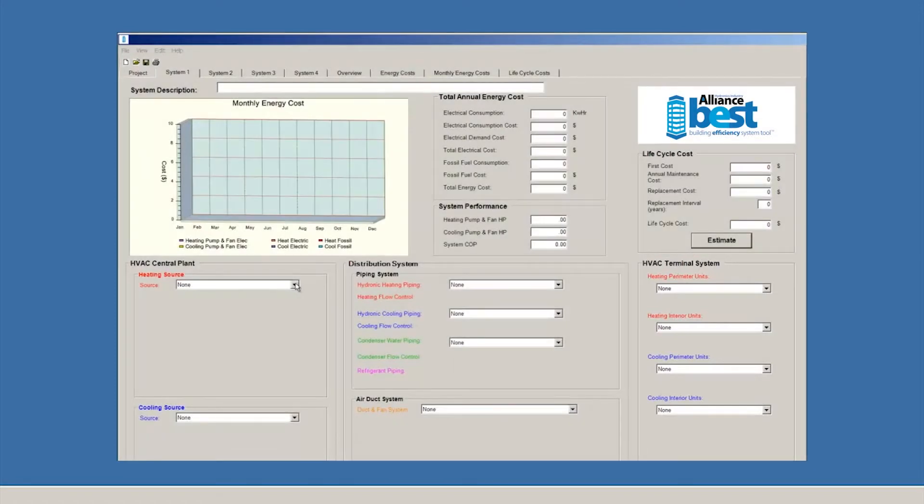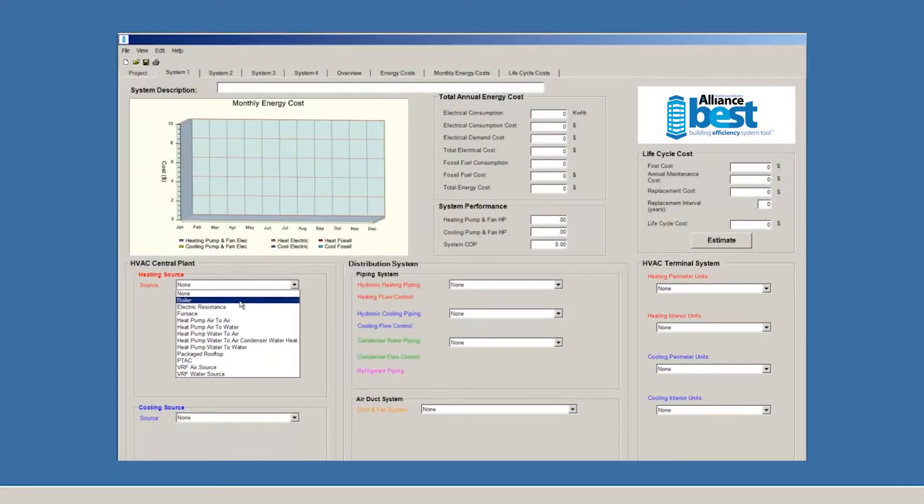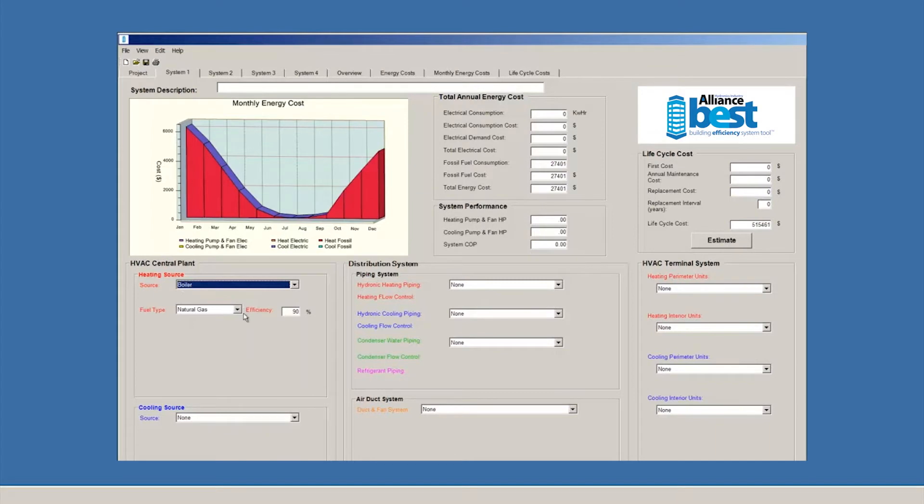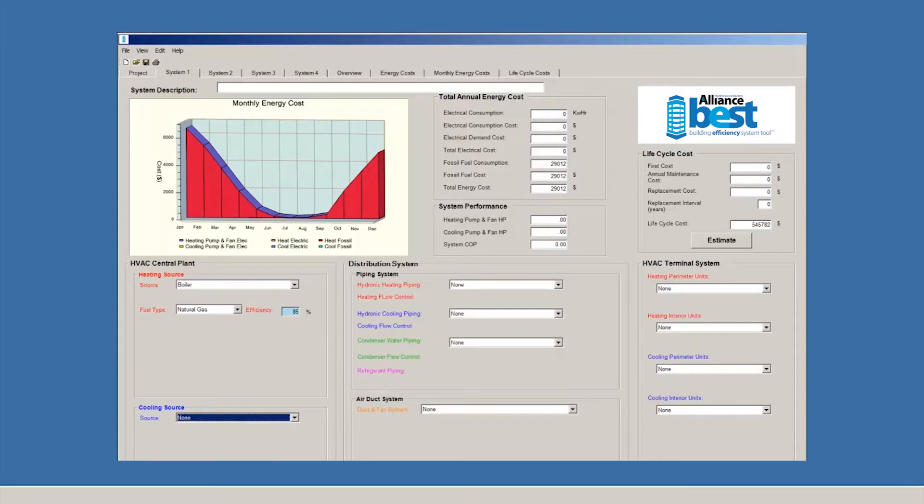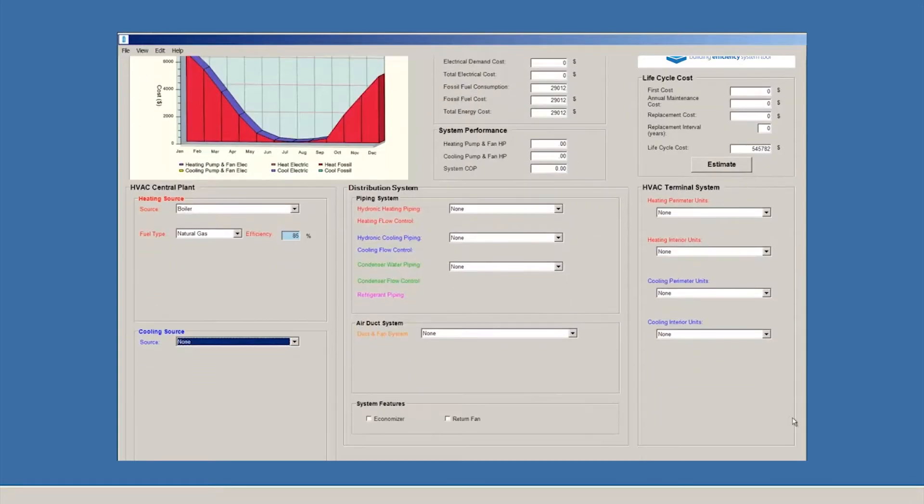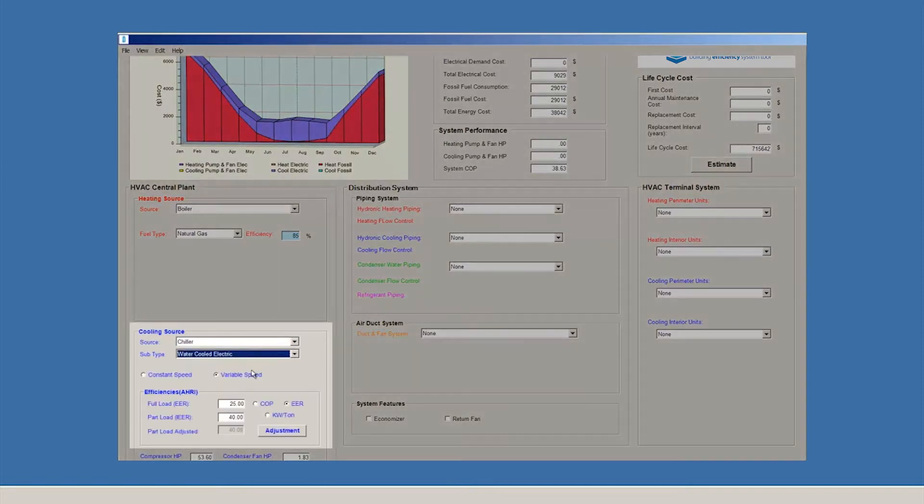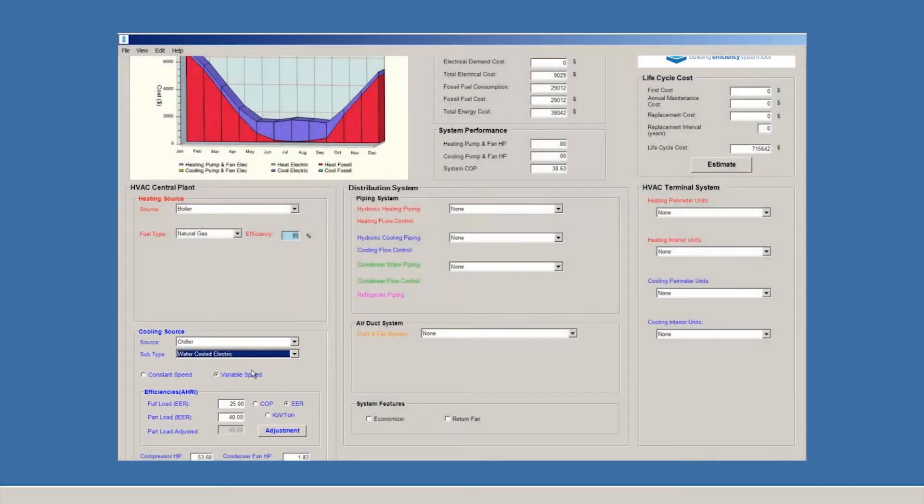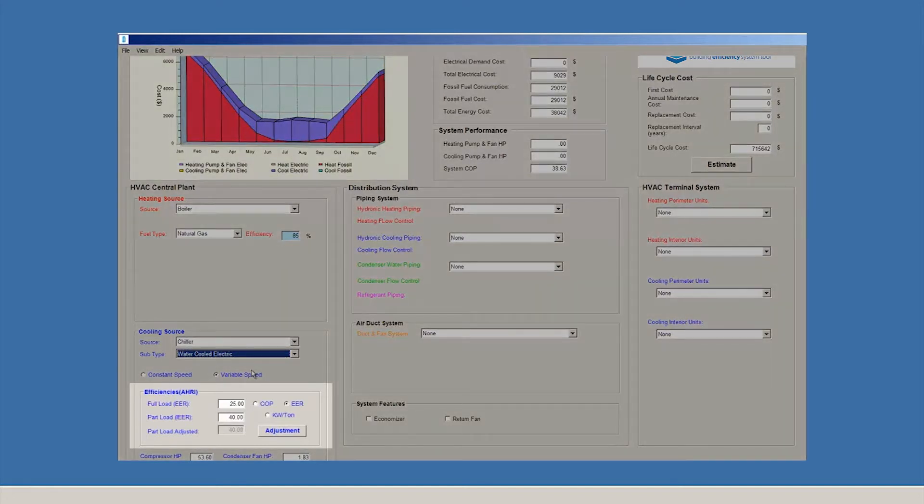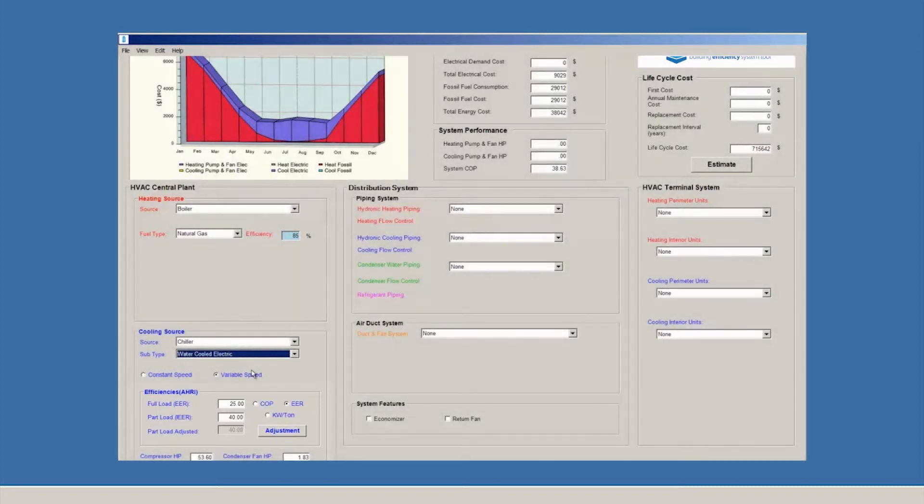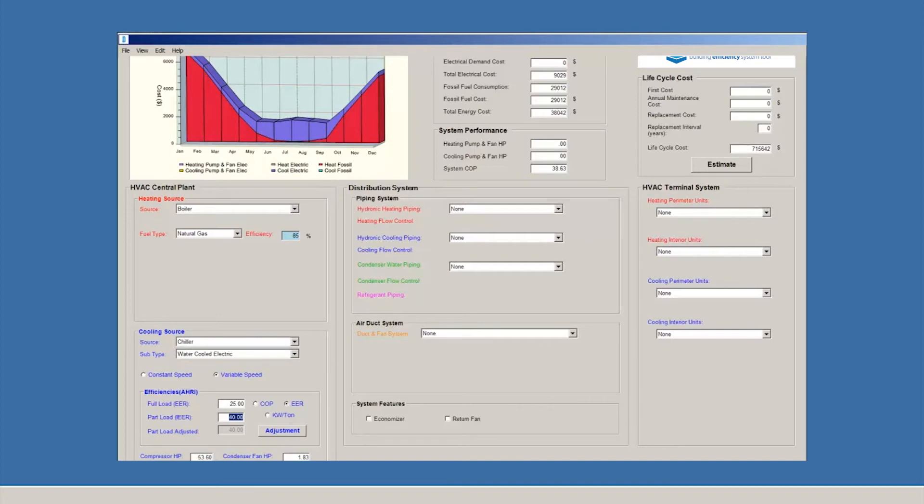Let's say, for example, that we wanted to model a boiler with natural gas as the fuel with an energy efficiency of 85%. Let's choose a cooling source. We'll make our cooling source a chiller, and we'll choose water-cooled electric as our subtype. The program automatically adds default values for the efficiency of this equipment. If you need to override the defaults, BEST makes it easy to do that. There are also default values entered for the EER and IEER fields. These can be overridden with custom values if necessary.